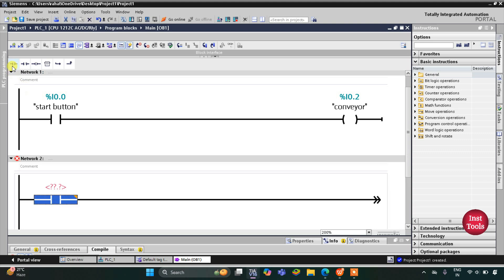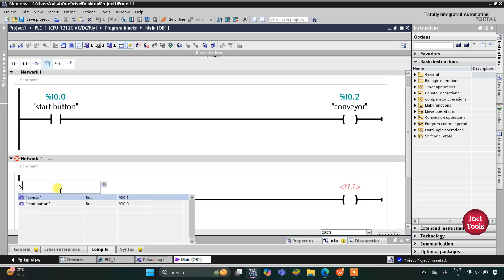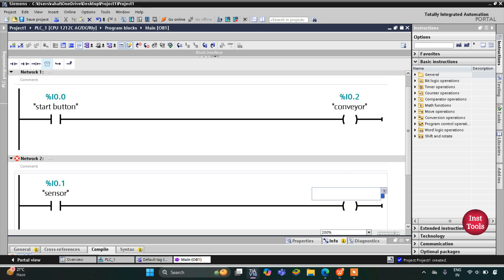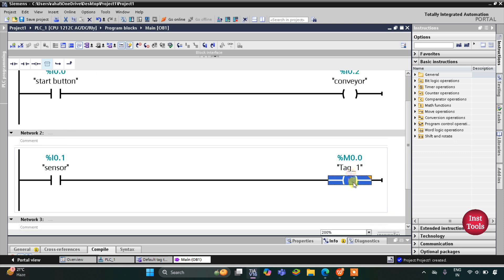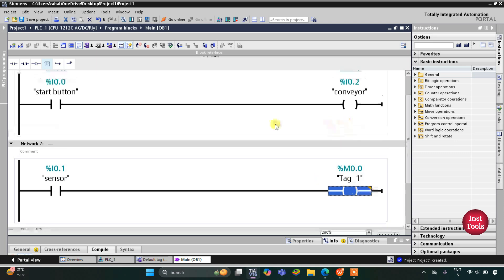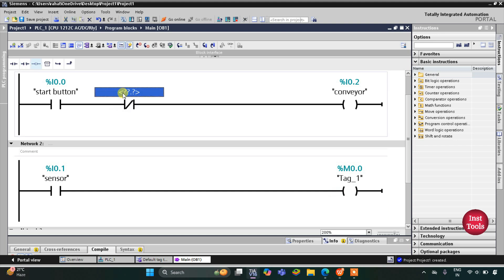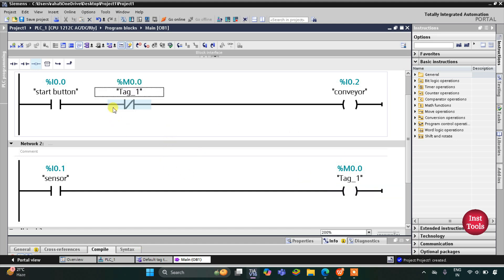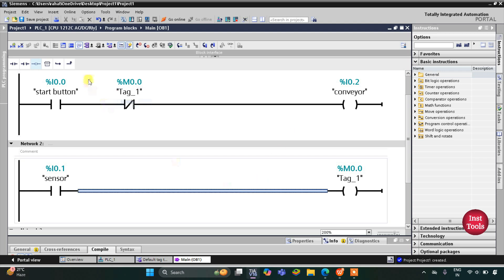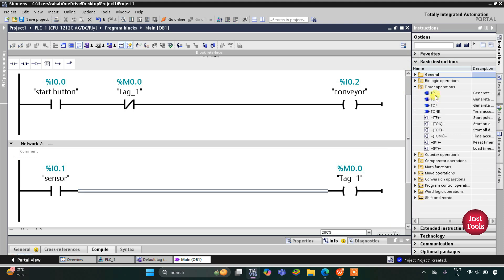I will insert one more normally open contact for the sensor and a coil for a memory bit M0.0. This is the memory bit that will turn on when the sensor detects the defect. This M0.0 will turn off the conveyor using a normally closed contact. When the sensor gets activated and M0.0 turns on, the circuit breaks and the conveyor stops. For this we will use a TP timer.